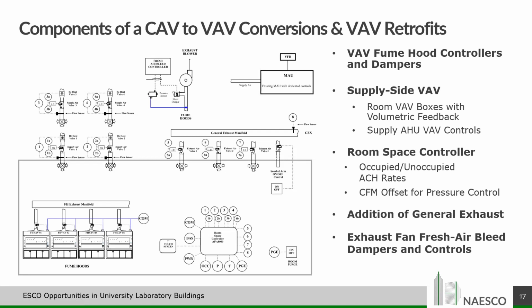And you have all that volumetric data for the exhaust, and then you control your supply to be a couple hundred CFM less than your total exhaust volume. That's how you control that negative pressure in the lab. That's how you keep the air flowing from the corridor into your lab and maintain that code requirement. And that's also the brains for occupied, unoccupied air change rates. You've got an occupancy sensor tied into this controller. When no one's been in there for a period of time, you can reduce your air change rates by reducing your general exhaust, and then your supply would be proportionally reduced, so you keep that CFM offset at a couple hundred.